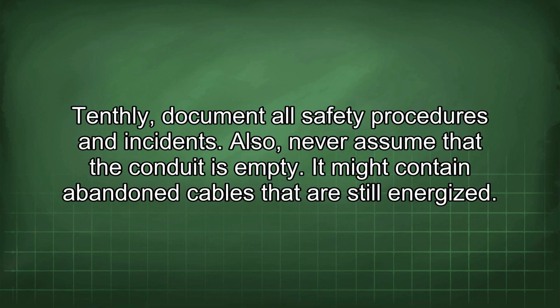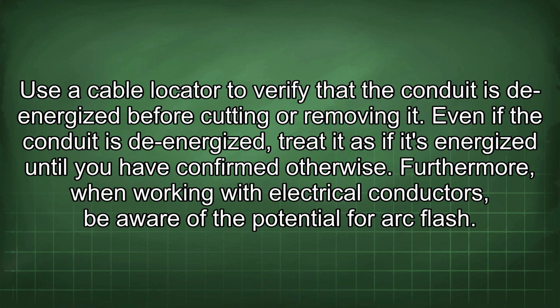Also, never assume that the conduit is empty. It might contain abandoned cables that are still energized. Use a cable locator to verify that the conduit is de-energized before cutting or removing it. Even if the conduit is de-energized, treat it as if it's energized until you have confirmed otherwise.